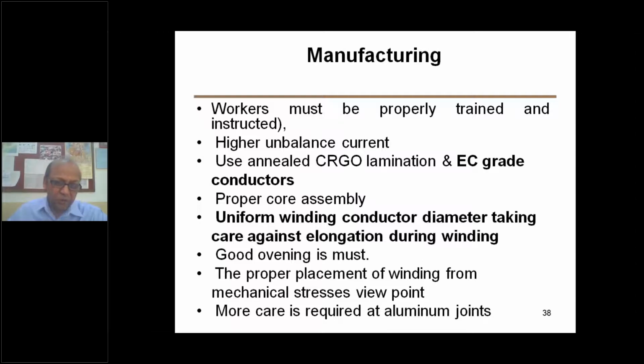Proper core assembly, no doubt, has to be done. Low loss transformer, no problem, you must be doing that. Then uniform winding conductor diameter, taking care against elongation during winding. Yes, this is very much true for aluminum wound transformers, that elongation is there. As I told you, creep behavior is poor, fatigue behavior is poor, therefore more elongation during the manufacturing itself. If that happens, that may cause the failure.